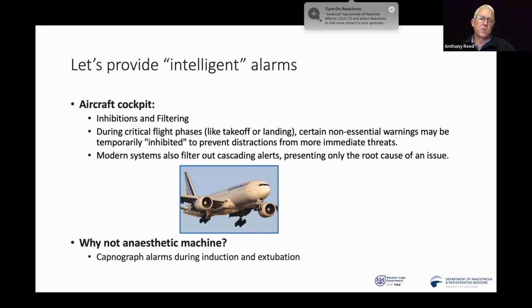And for me, the classic example is the anesthetic machine during a general anesthetic. During a general anesthetic, we start the induction, we get the patient deep enough, and then we're either going to put in a supraglottic airway or we're going to use the endotracheal tube and intubate the patient. And at that point, we put the airway down, the mask and the airway circuit, and now we have to work with the patient's airway. And then what always starts happening is that the capnograph tells you there's no CO2 and starts alarming, and then it'll say there's no pressure, and we have to ignore that.